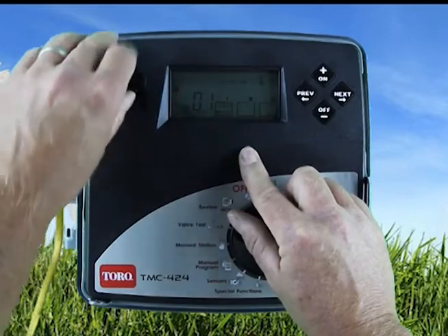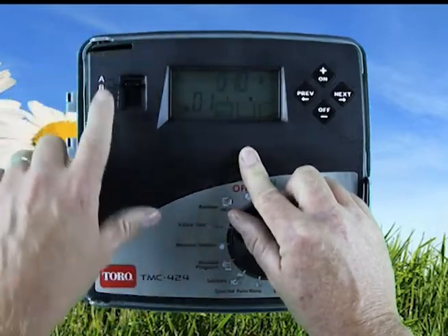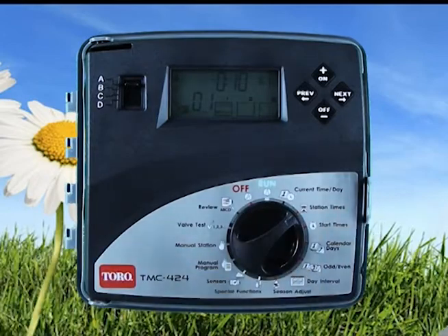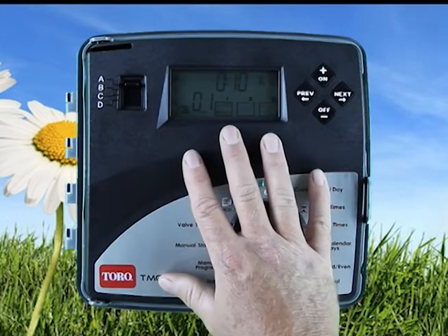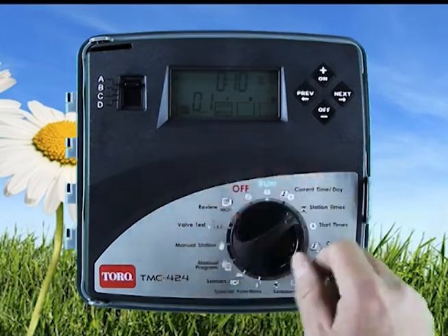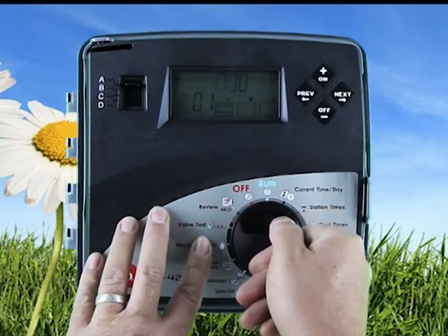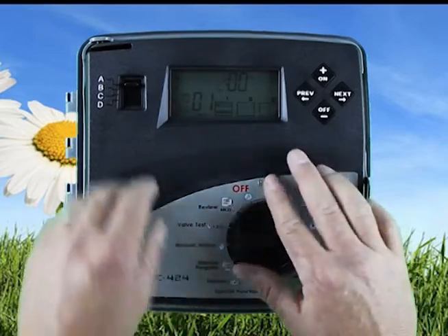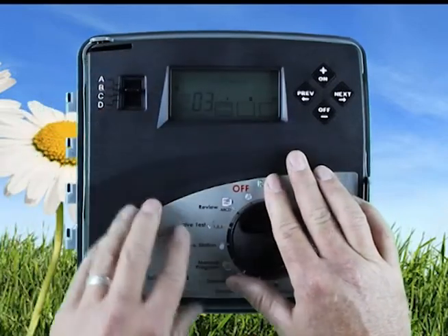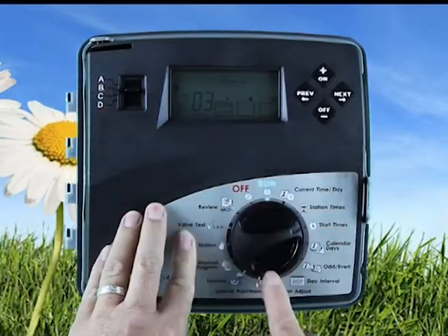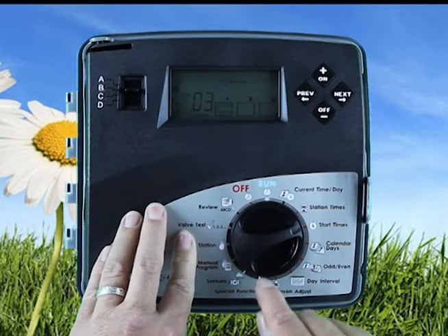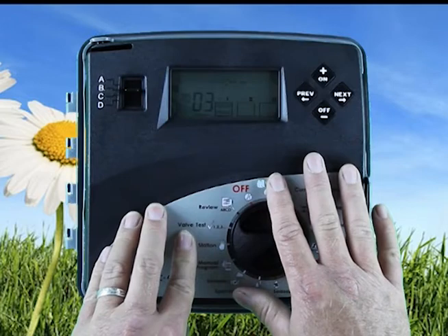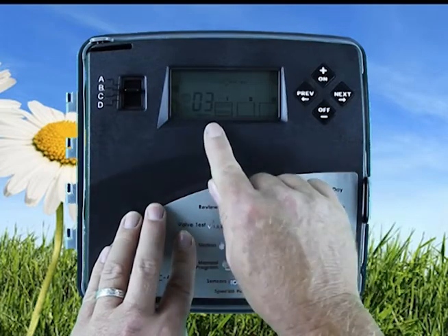Now, the best way to look at A, B, C, and D is as if we had 4 different controllers. This clock A is running for 10 minutes on each station and it has a start time at 2 a.m. If I come to B, it would be a third start time because A has 2 start times. This box is capable of doing up to 16 start times. So right now I would use a third start time.